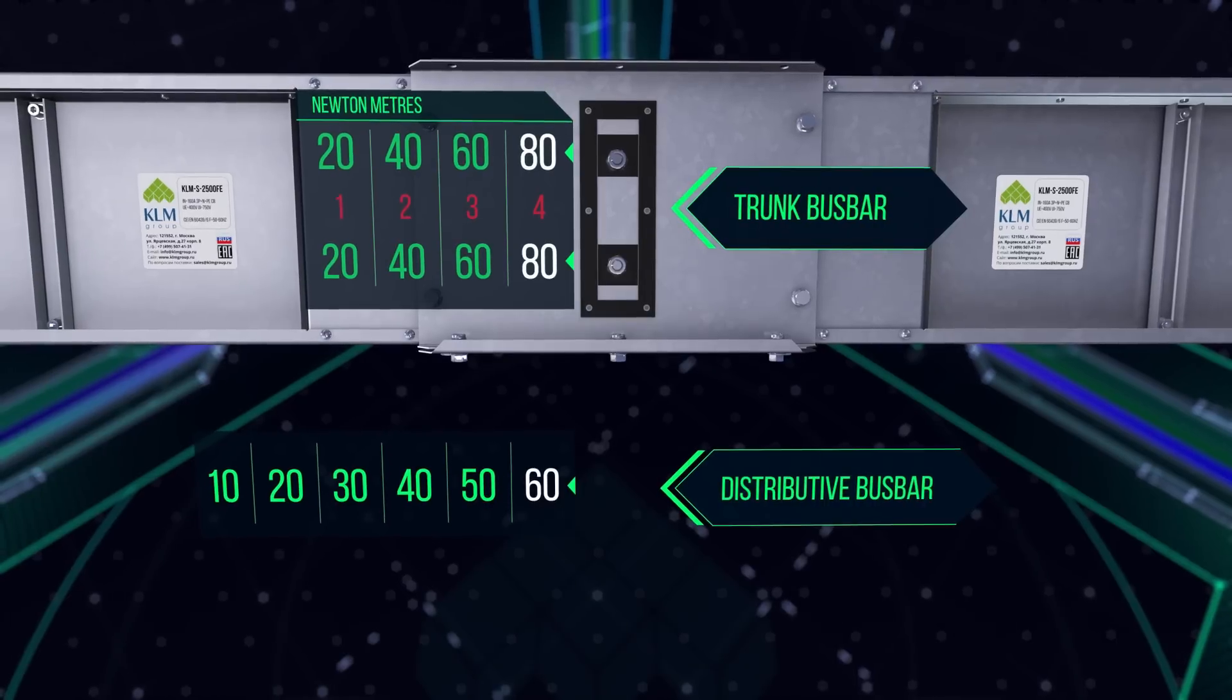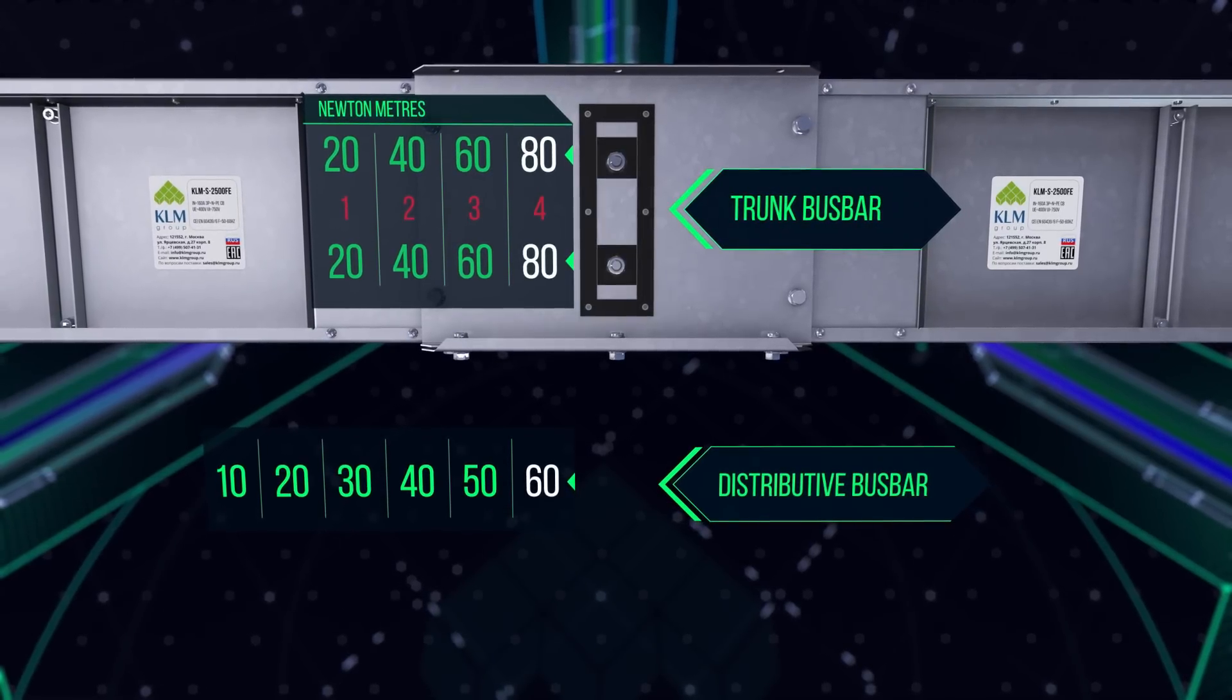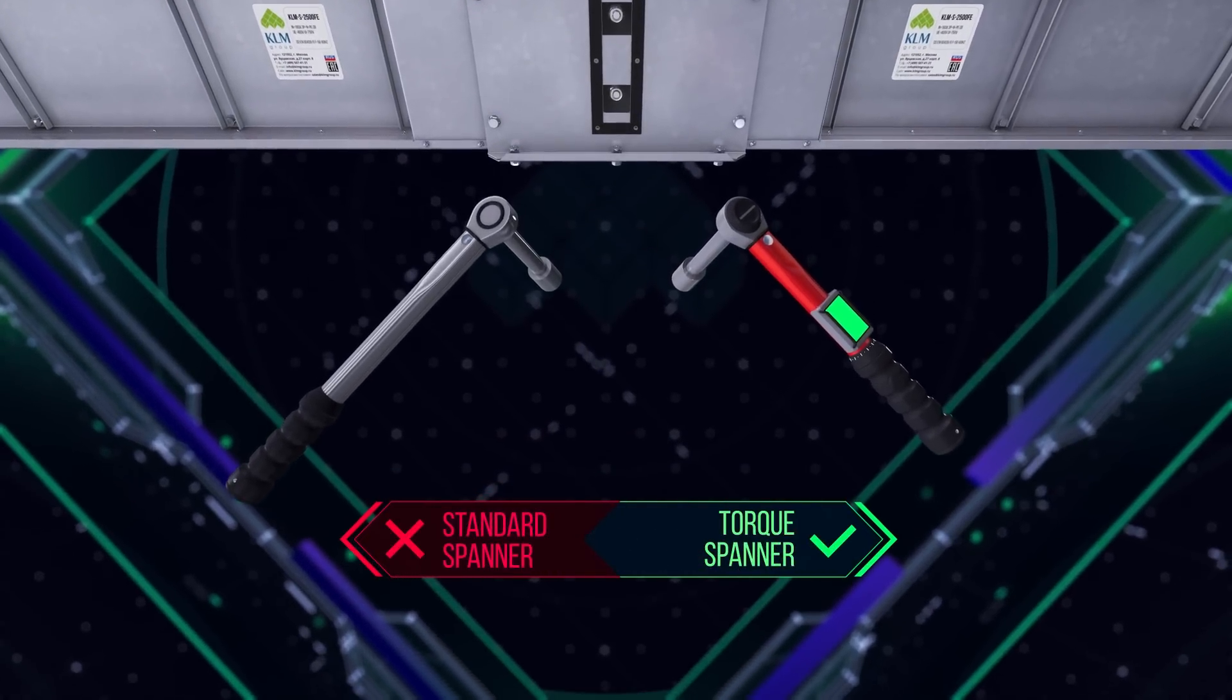For a distribution bus bar trunking system, the clamping bolts must be tightened in increments of 10 newton meters until a torque of 60 newton meters is achieved. The clamping bolts must not be tightened using a standard spanner. Doing so may cause failure of the junction unit.